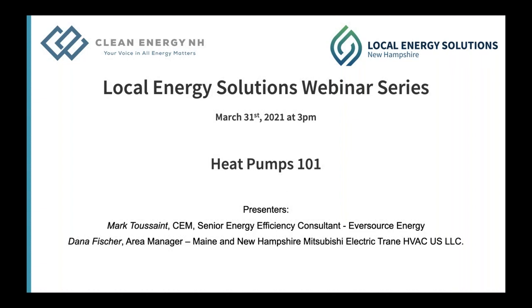Earlier there was a question about installing a system in a maintenance garage, and I think James just emailed me a follow-up related to concerns about dust. If you're going to be installing a heat pump in an environment where there's going to be a lot of dust or sawdust or dirt and debris, then an elevated cleaning cycle may be appropriate, or it may be appropriate to install a ducted system where you could have a filter. If you have a conventional furnace filter leading into your heat pump, you'd be able to put in whatever kind of filter would be required to remove dust from the air, which is not only better for the heat pump, but also better for all the people and things in the environment.